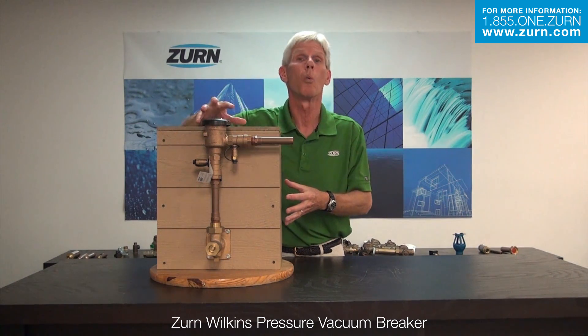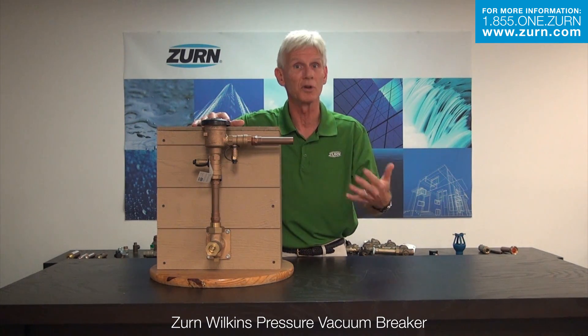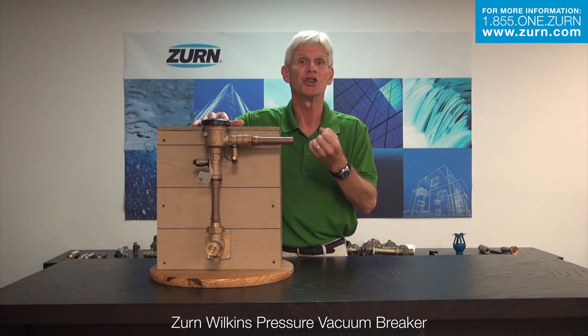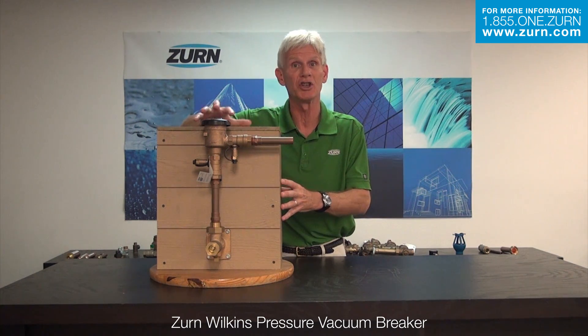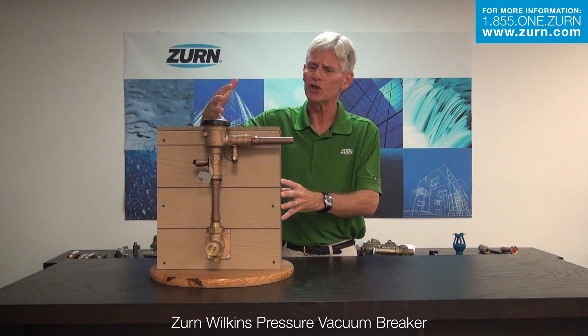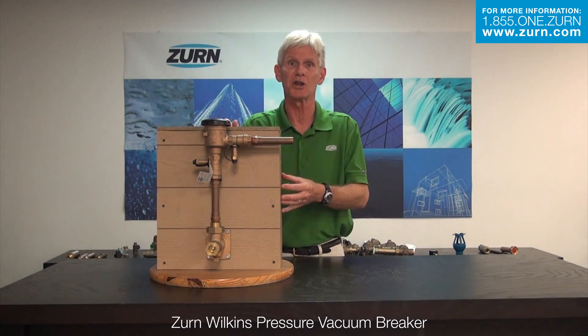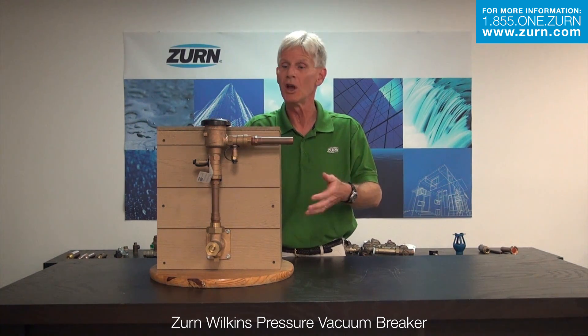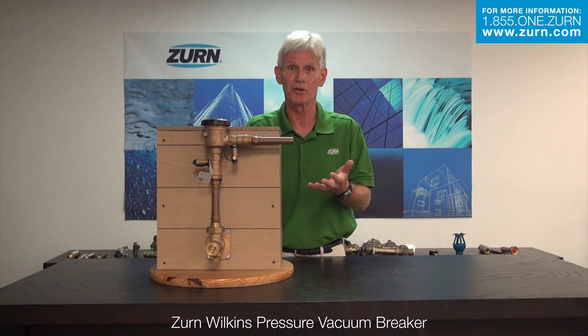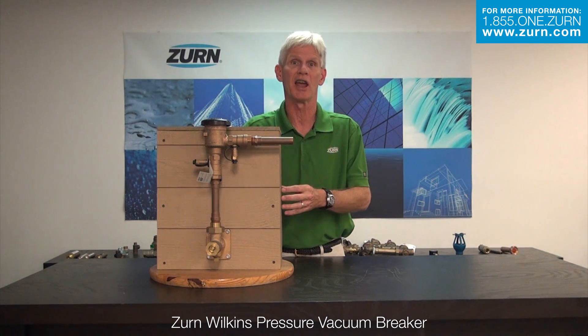Any worn component should be replaced. If we do replace worn components, once again we're going to want to induce a high flow through the valve once you get all the water turned back on, and shake all of the air out of that valve — because again, that air can cause pulsation and chatter. In the event that you have any questions, feel free to contact us here at Zurn Wilkins. We're happy to talk to you, give you additional guidance, and do anything we can to make sure you're very happy with the product and that it works exactly to your expectations.